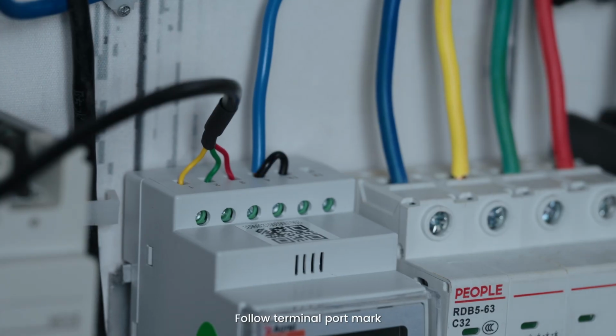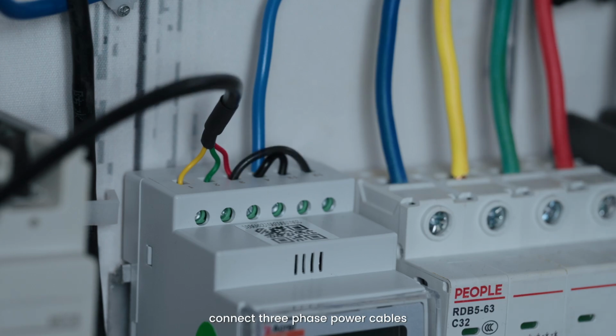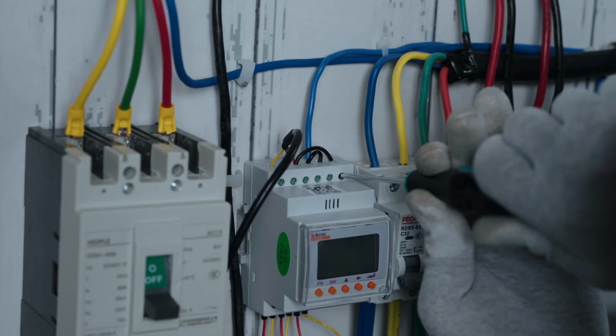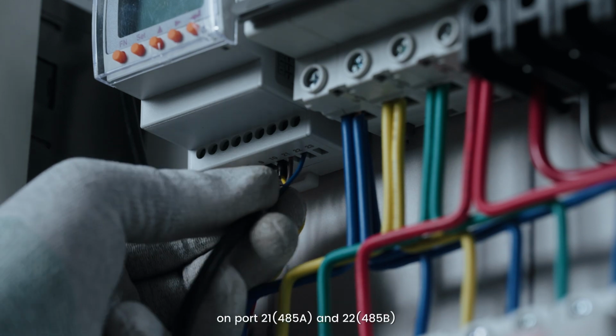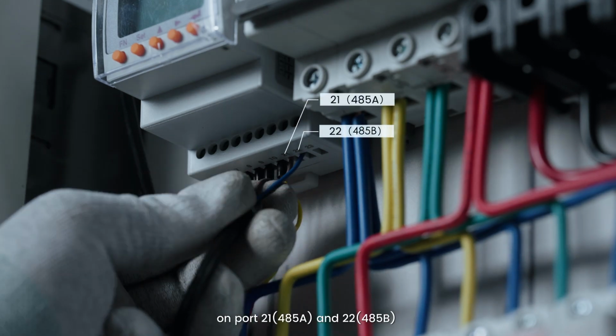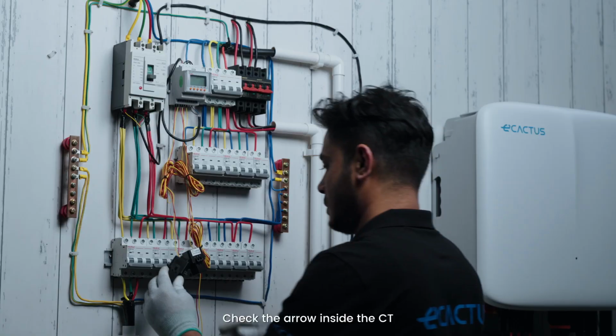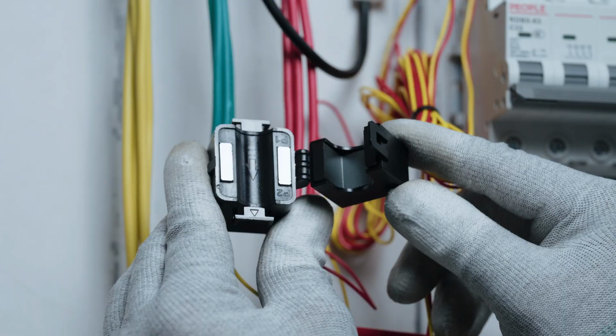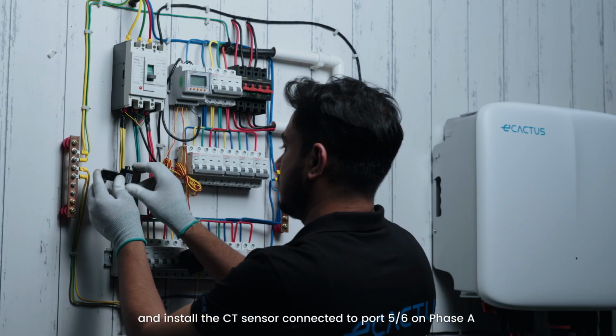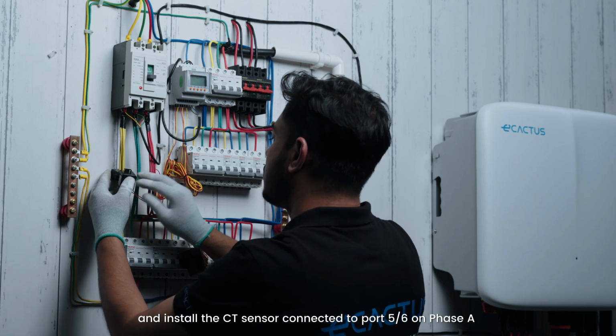Follow the terminal port mark. Connect 3-phase power cables, neutral cable and jumper cable in order and tighten them well. Connect meter communication cable on port 21 485A and 22 485B and tighten them well. Check the arrow inside the CT and install the CT sensor connected to port 5-6 on phase A.